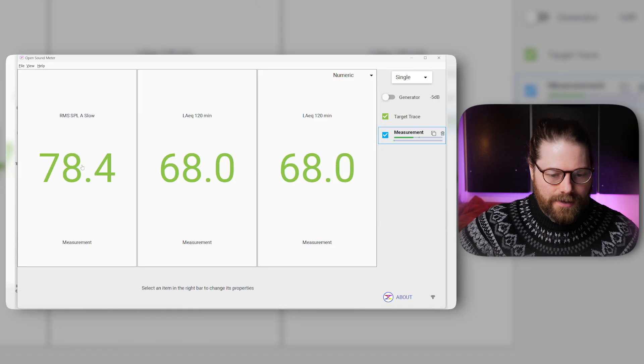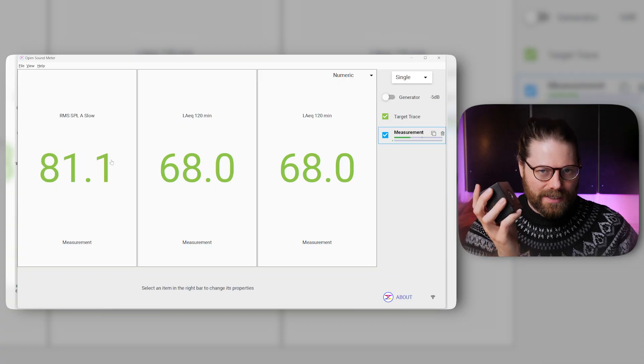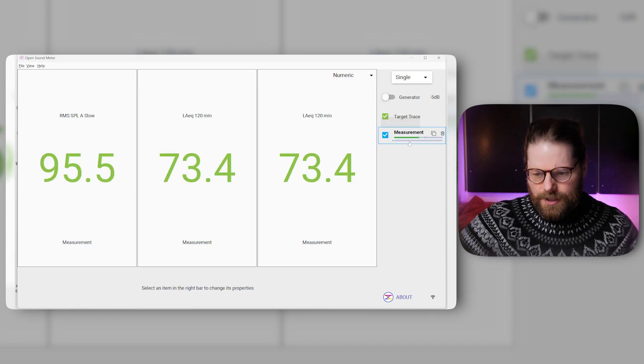Now we need to calibrate this microphone. I get my microphone, put it on the calibrator, and turn it on — you'll see the signal appear in Open Sound Meter. I need to be nice and quiet. Down at the bottom there's a button that says 94 — 'apply estimated gain for 94 dB SPL' — I click that. What that's done is tell Open Sound Meter that the input level it's seeing right now is 94 dB. Now the microphone is calibrated. I check it shows 94 dB — it's showing 95, a bit weird — so I'll double-check the calibration again.